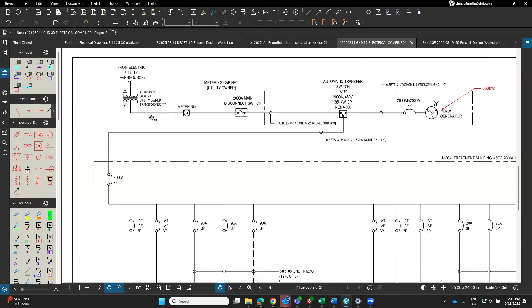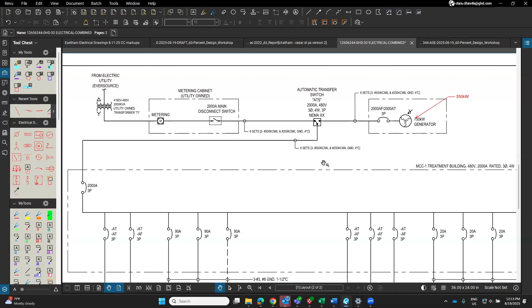Then we'll go to all the metering equipment, the disconnect switch, and the automatic transfer switch for the standby generator. I've been working with a bunch of the different generator manufacturers we specify to make sure we get the lowest decibel rating possible, the most noise cancellation. Some of them might require a custom enclosure for the generator, but we're working with the manufacturers to get the highest level of noise cancellation so it will be the quietest. It will be a 550 kW natural gas generator, and Cummins is our basis of design.